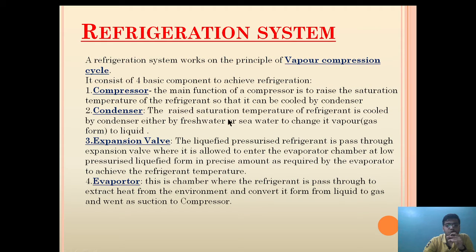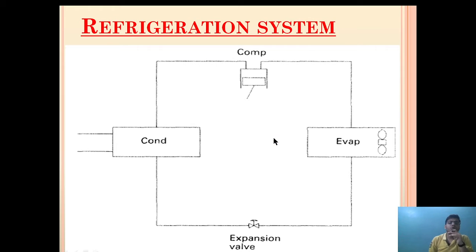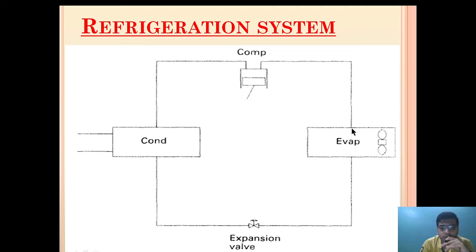The raised saturation temperature of the refrigerant is cooled by the condenser, either by fresh water or seawater, to change its vapor form. The whole system can also be subdivided into two parts: a high pressure system and a low pressure system. From the evaporator to the compressor, this part is the low pressure zone — the gas is in low pressure. From the discharge of the compressor to the inlet of the expansion valve, this area is high pressure.